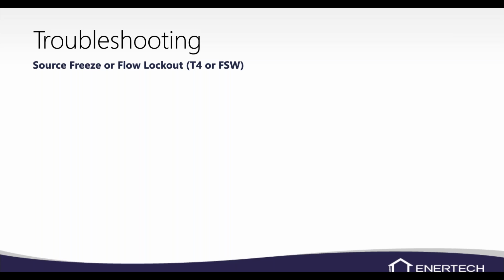If you do have wires hooked into those spade connectors on the FS terminals, then you have a flow switch, which is basically a paddle switch that's in the source water line, and the water closes that switch. So you'll have to know which exact unit that you have. The newer units are going to that T4 sensor.